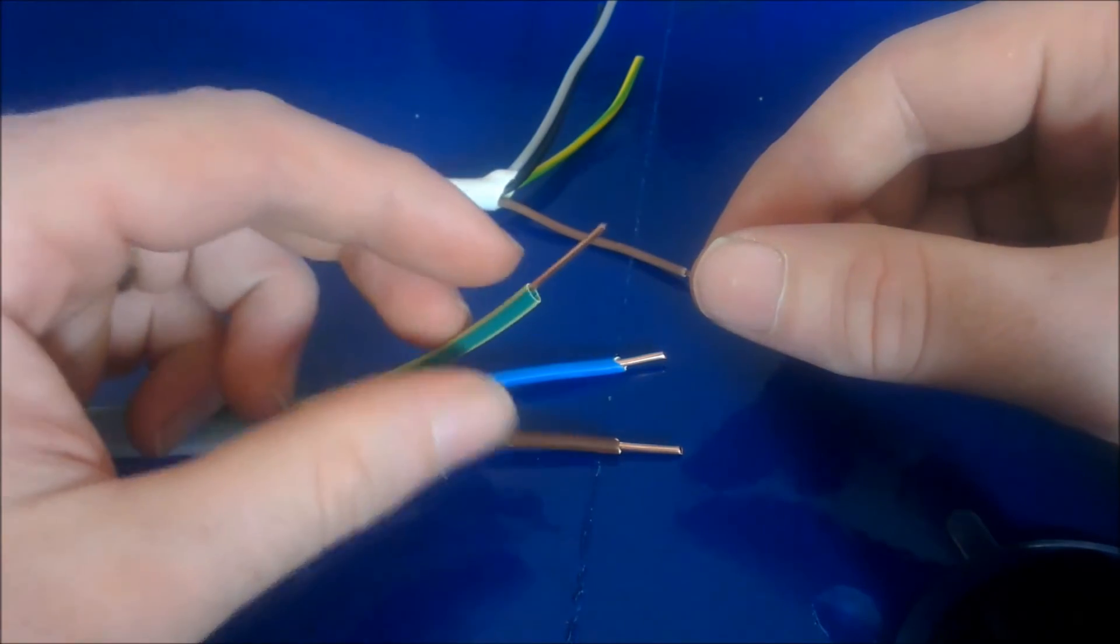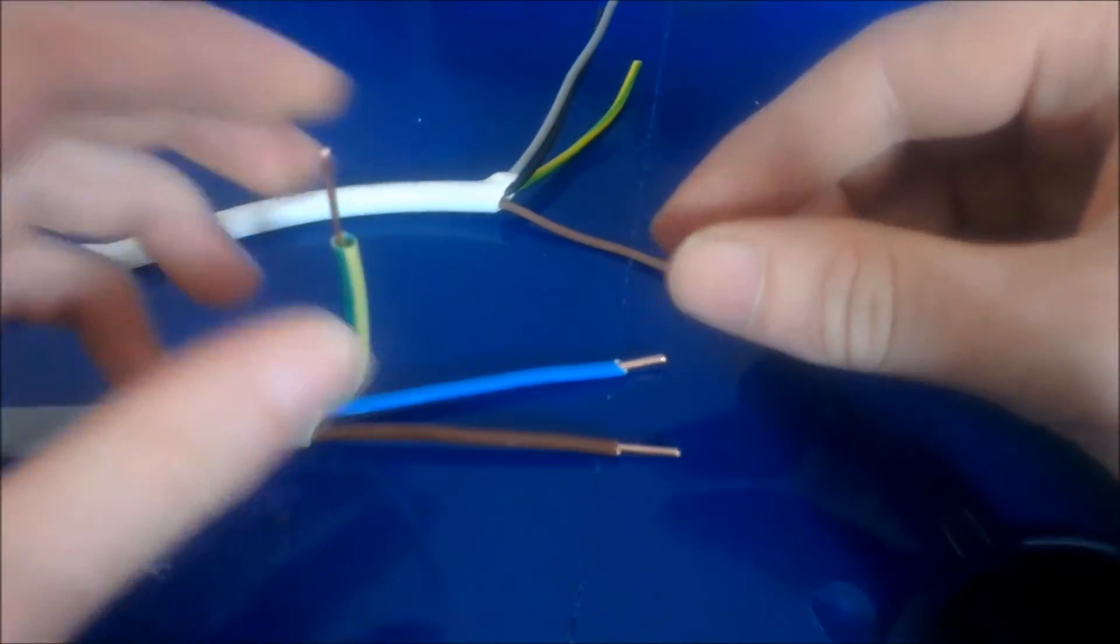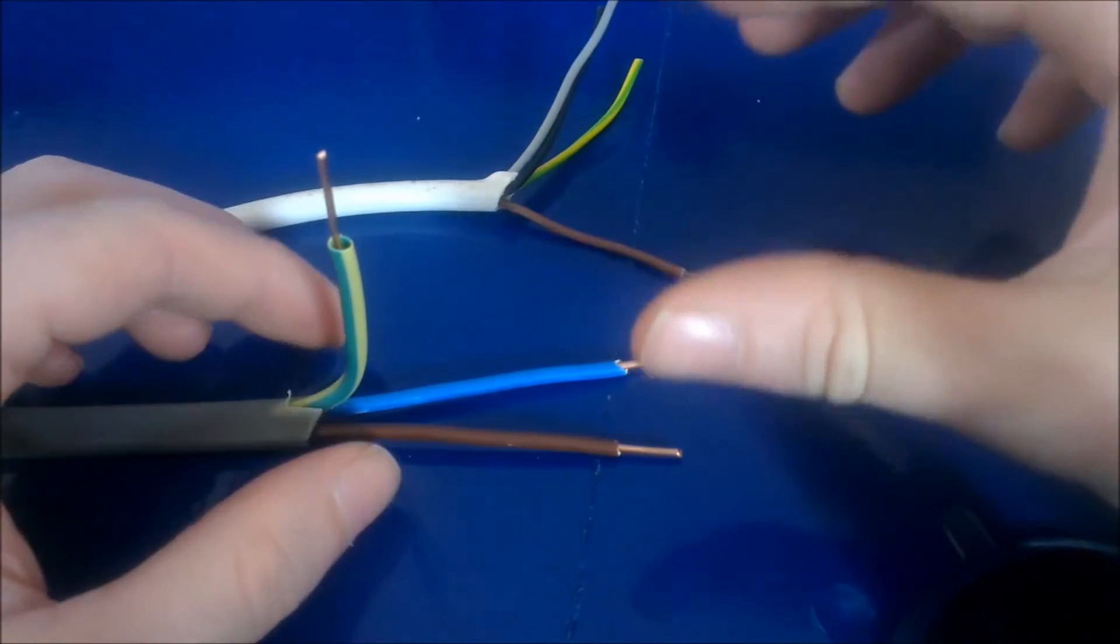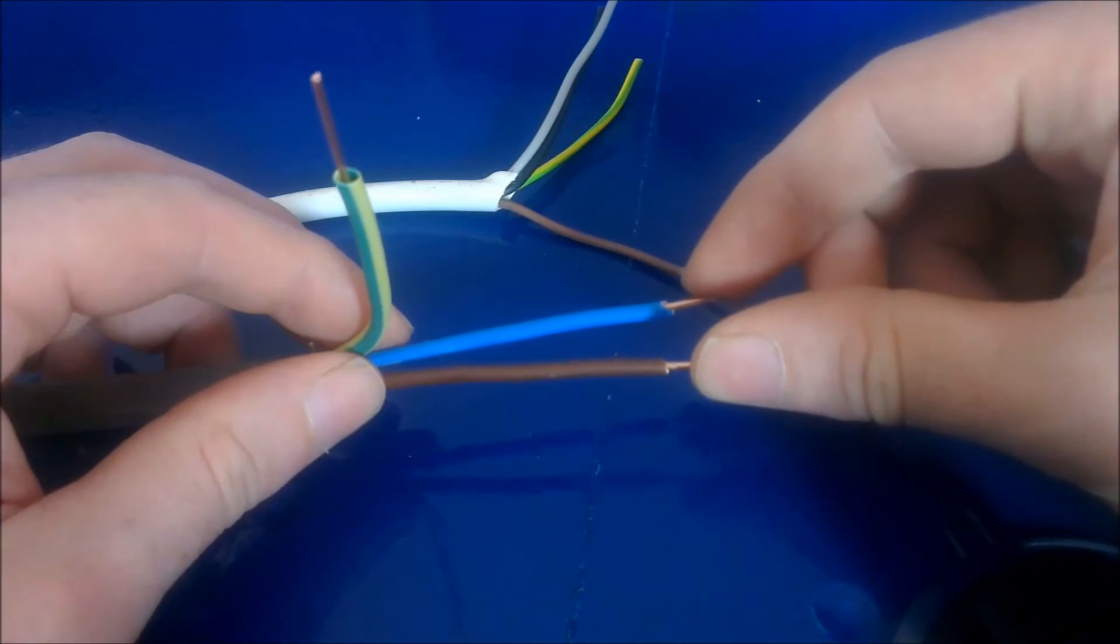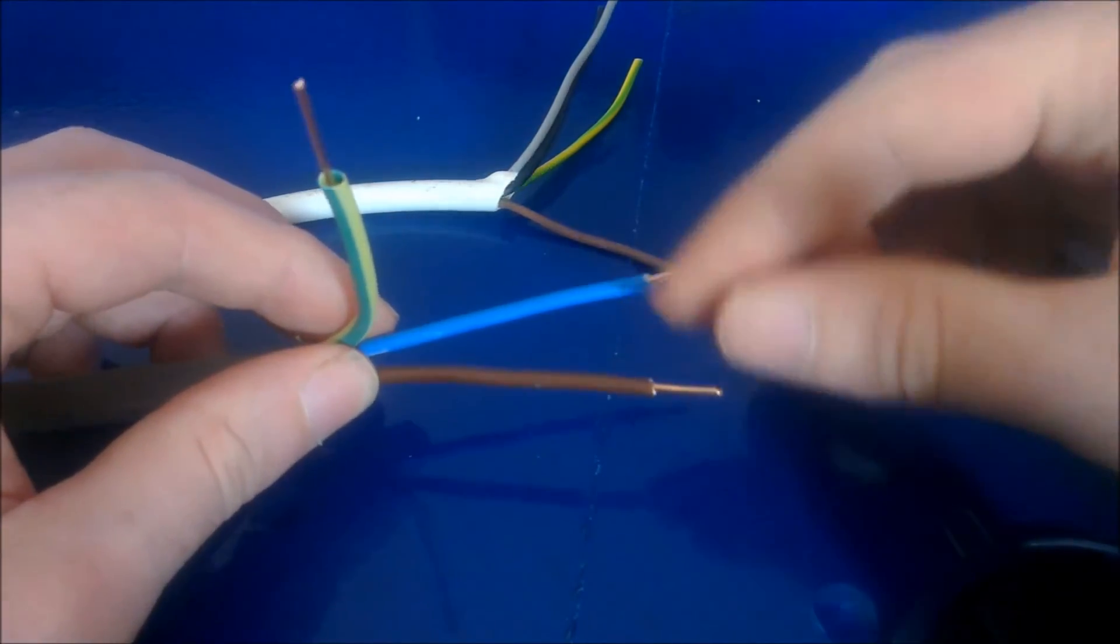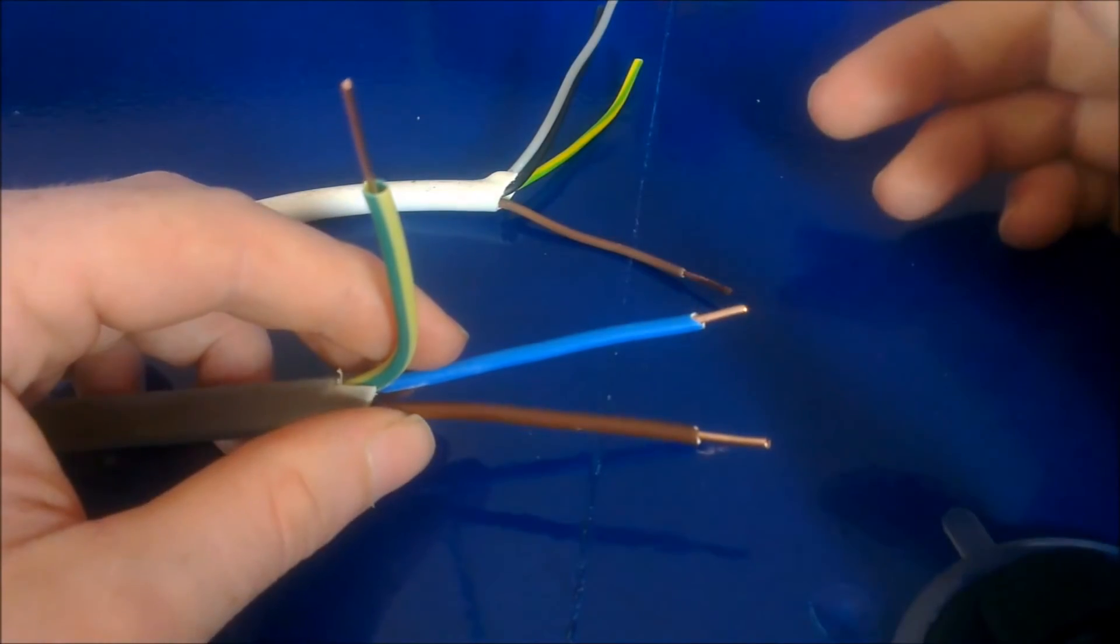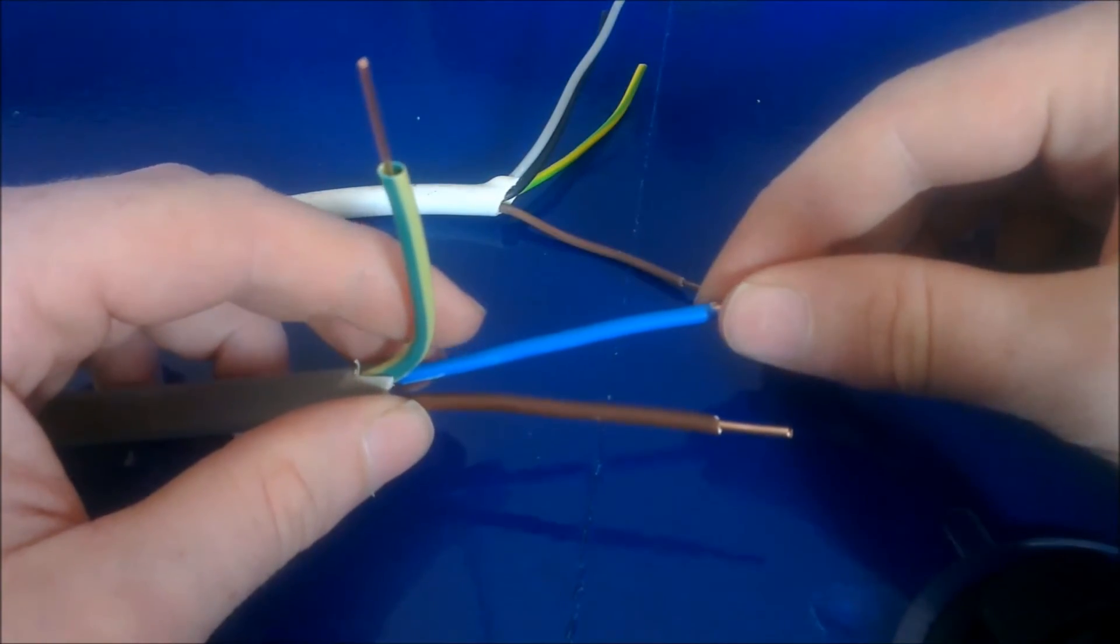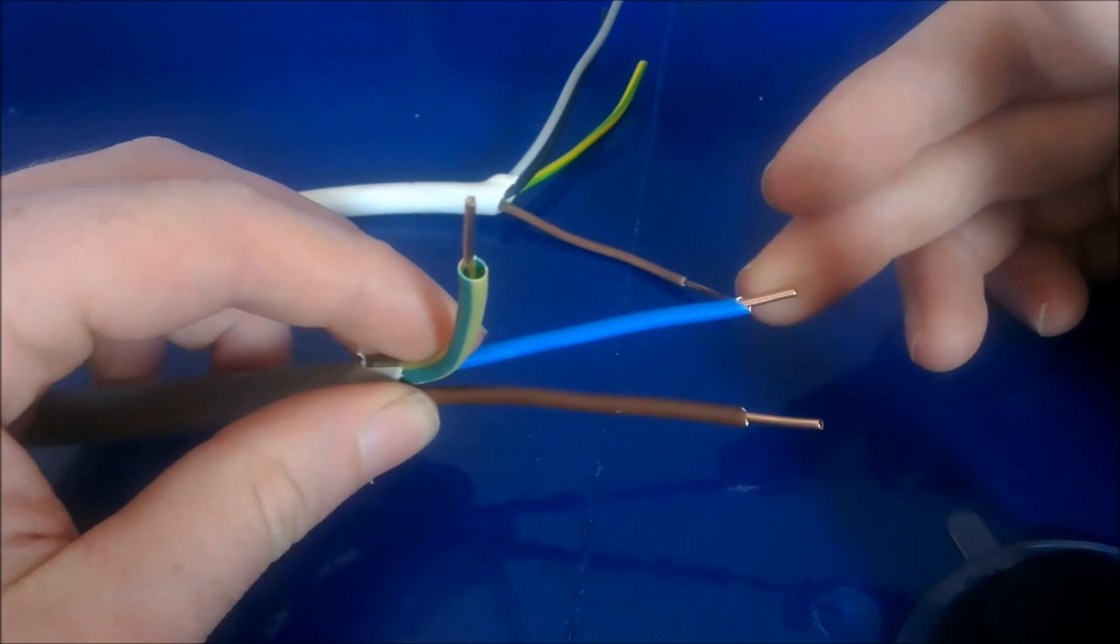And then the earth is 1.5mm. So 1.5mm is the type of cable—you can get 1.5mm twin and earth, exactly the same, only the live and neutral conductor is 1.5mm and the earth is smaller again, it is 1mm. That would be the type of cable used for lighting circuits, so it's slightly smaller than this.